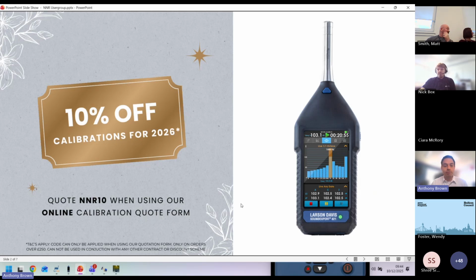Your meters need calibrating every 2 years, and your calibrators need calibrating once per year. If you're unsure of the calibration dates, there should be a label on the back of your meter, so have a look now, just turn it over. It should show the date it's due for calibration.